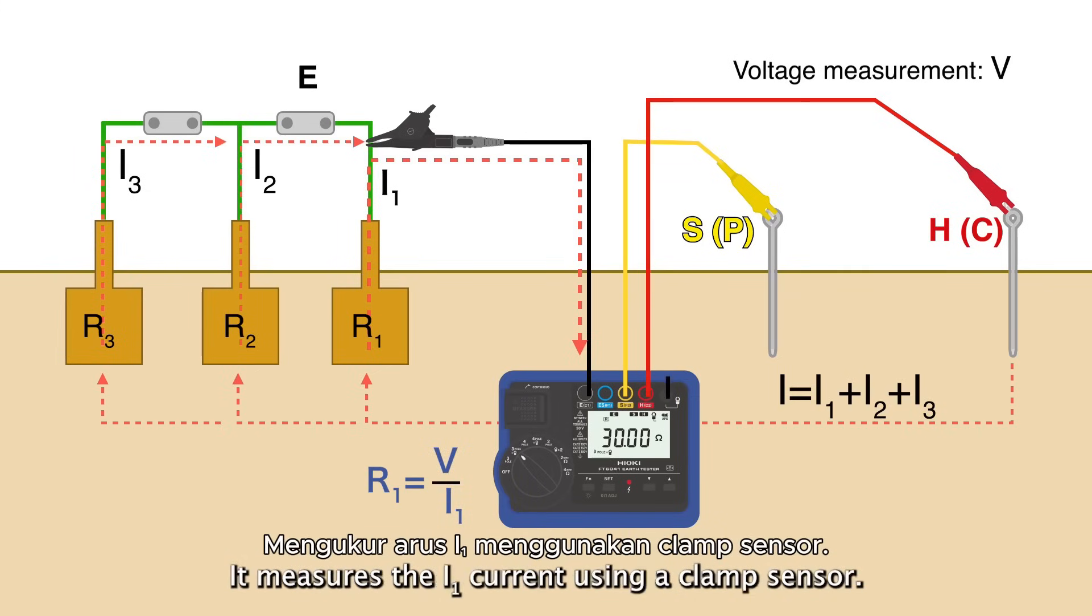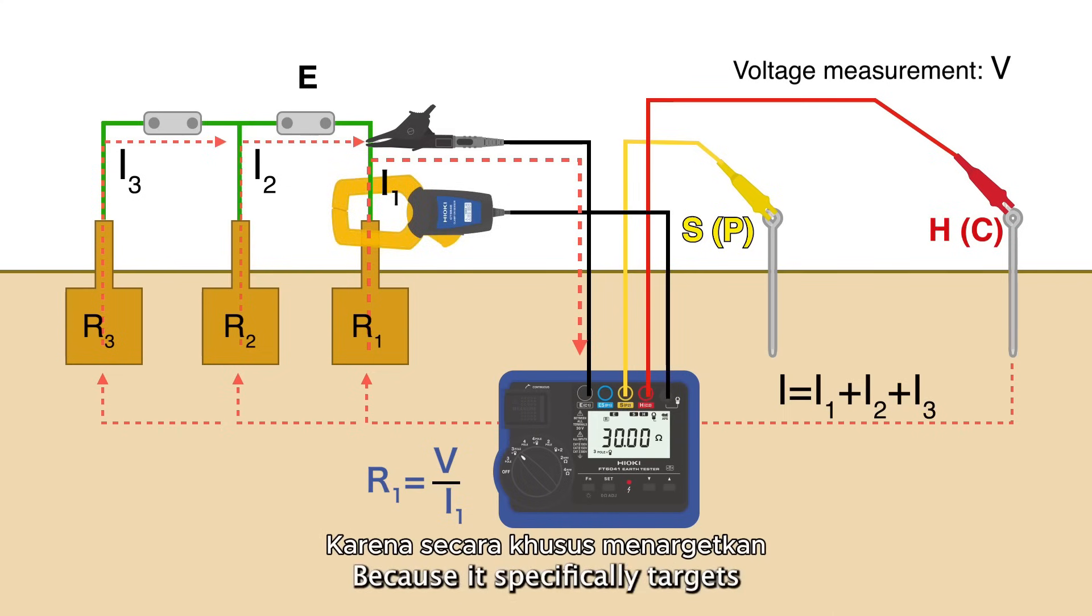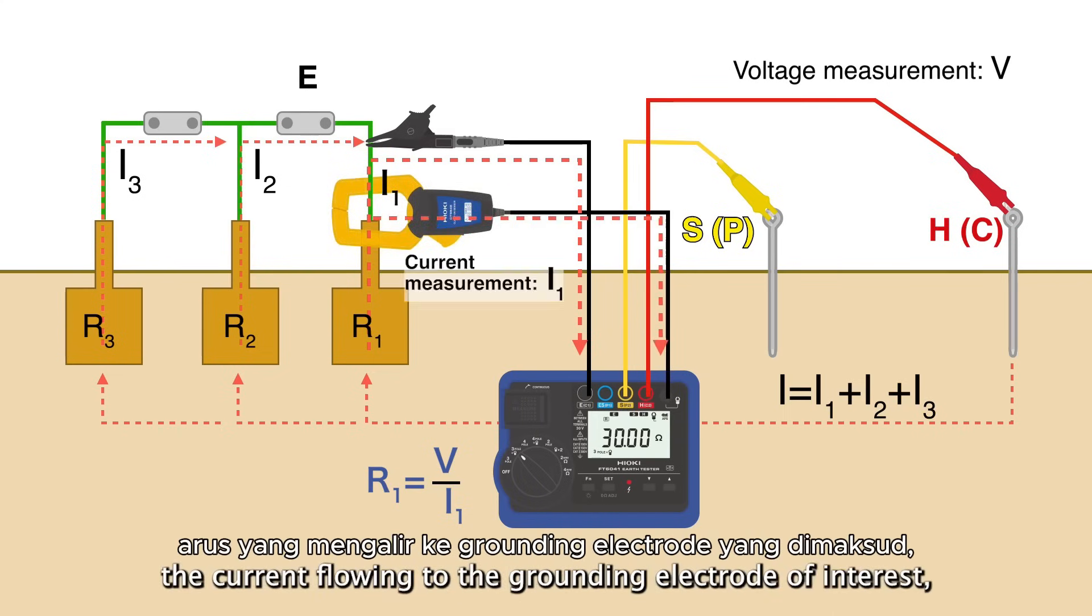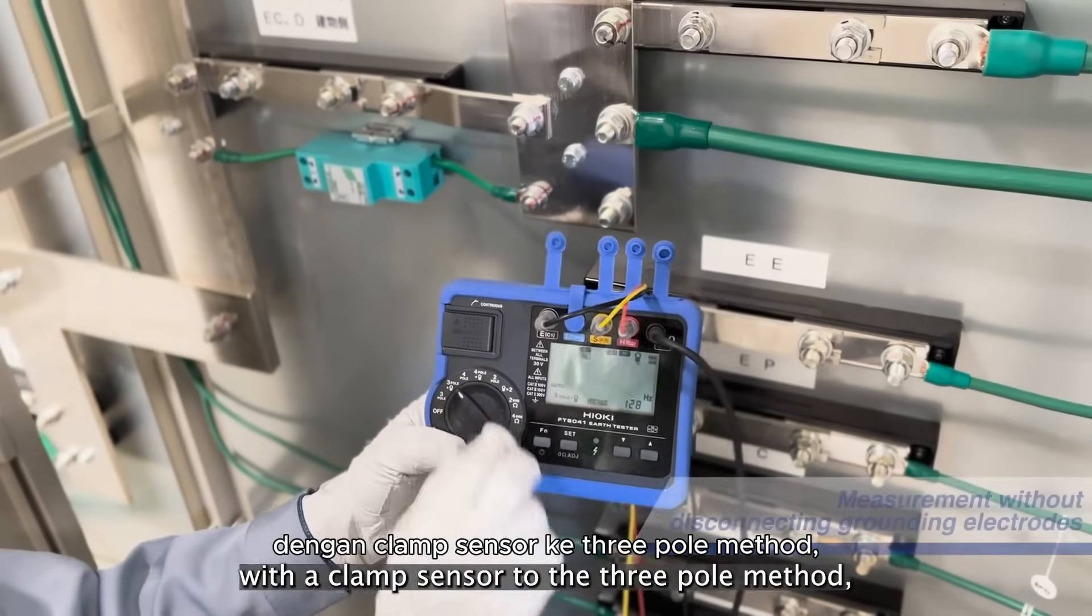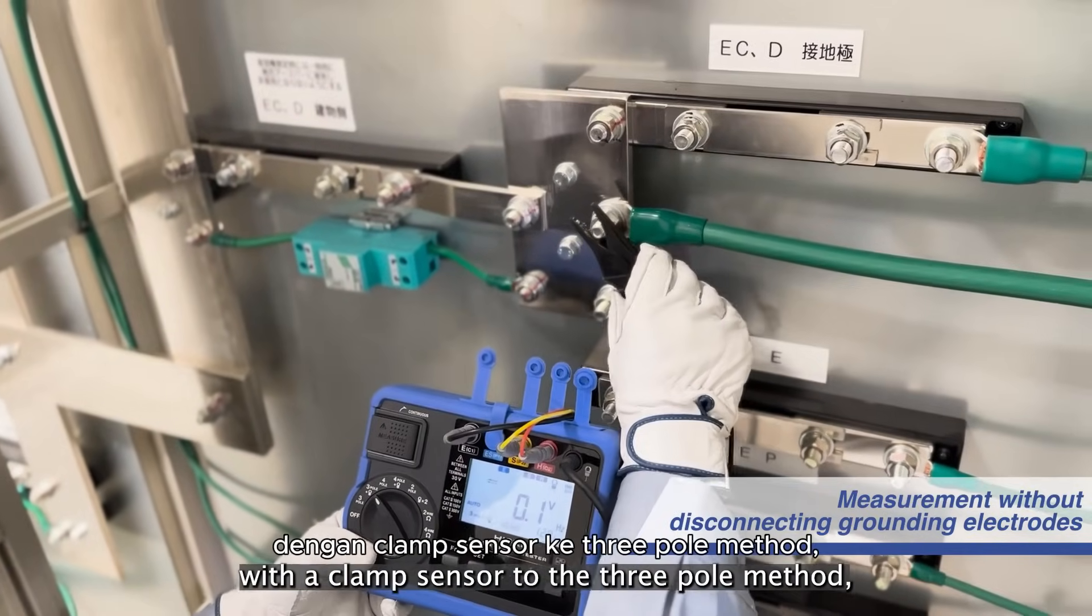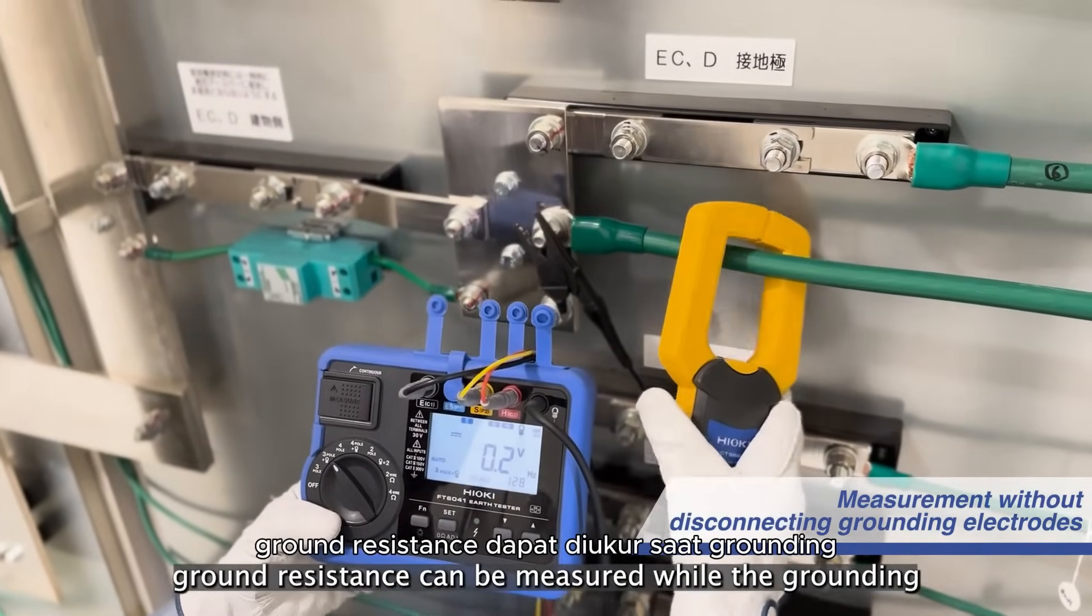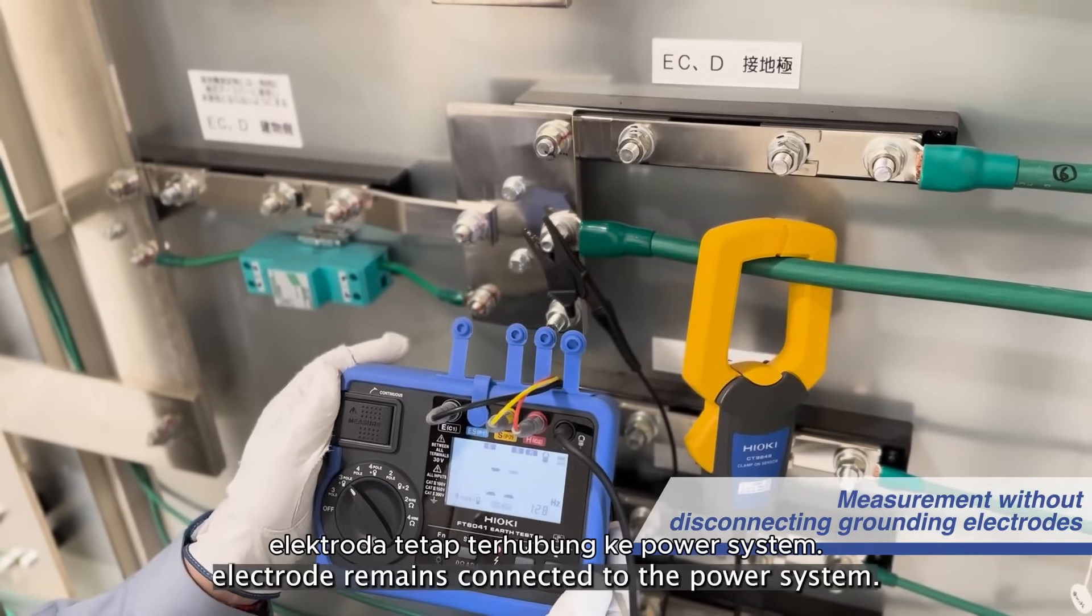It measures the I1 current using a clamp sensor. Because it specifically targets the current flowing to the grounding electrode of interest, the measurement is not influenced by other grounding electrodes. By adding current measurement with a clamp sensor to the 3-pole method, ground resistance can be measured while the grounding electrode remains connected to the power system. This eliminates the need for disconnecting the grounding electrode, which saves time and effort on measurement tasks.